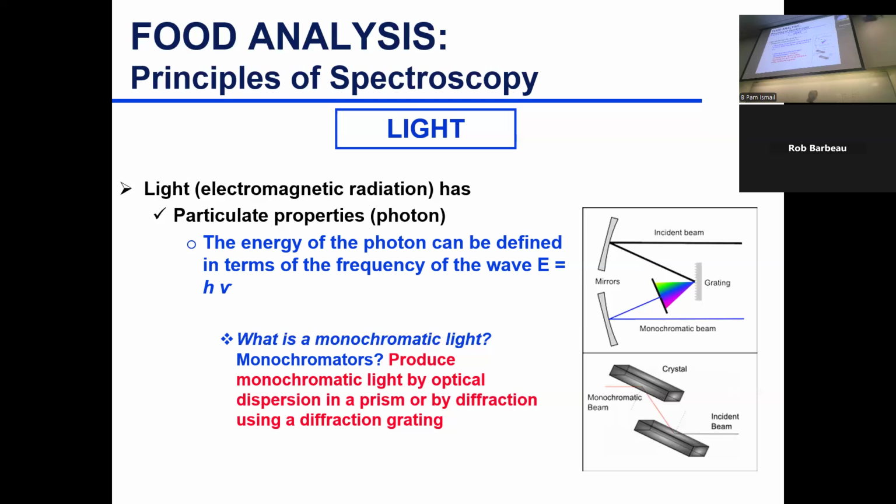or your flow cell where your sample is passing through, like an HPLC, in a tube versus the flow cell. So that slit, the system can be controlled and can be moved up, down, and then you can have different wavelengths reaching your sample. That's why we talked about variable wavelength detector, because we can move it. We can tell it to move up, down, and select for a particular wavelength to go through and go to your sample.